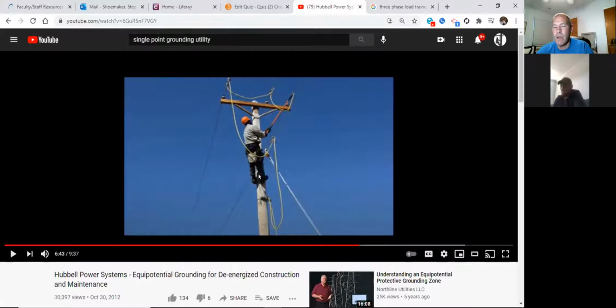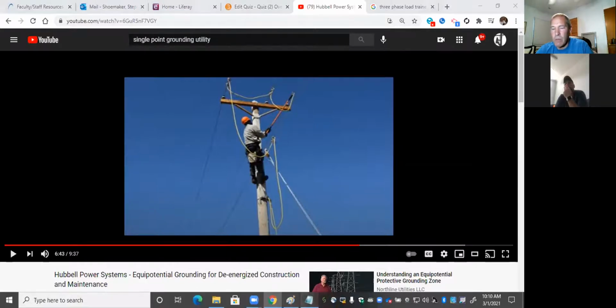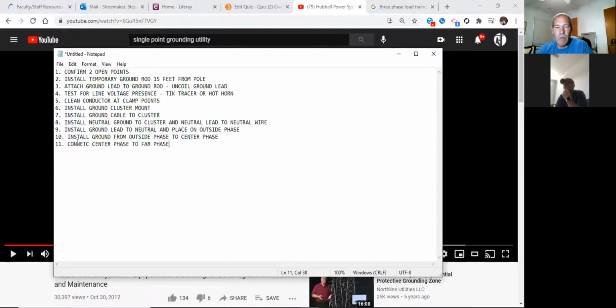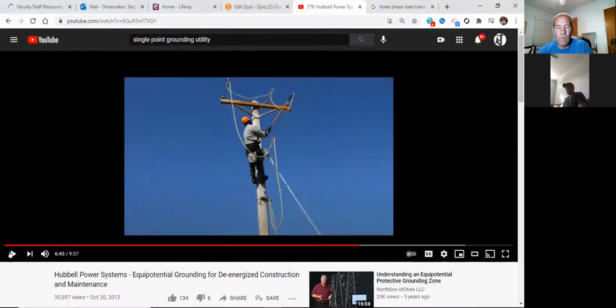You have to be working in this zone. The reason behind it is, if your feet are below the cluster bar, which is right here, and you're working with your hands above it, is there a difference in potential? We talked about potential before. Yes, there is a difference in potential. Although minute, it still exists. That's why you have to have your entire body above the ground cluster. So am I caught up in my notes? Connect, even though I can't spell, connect center phase to far phase conductor.